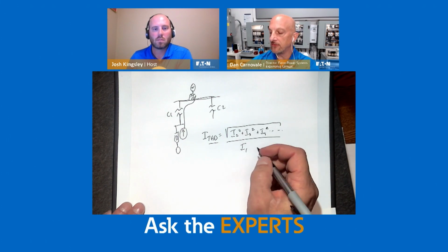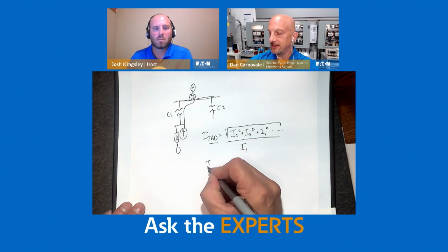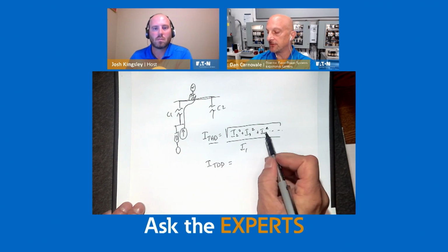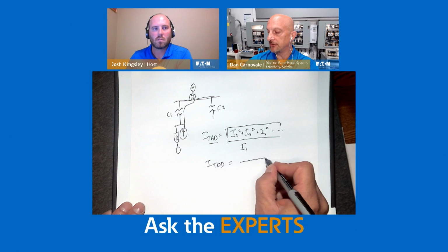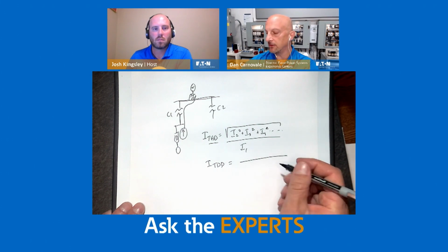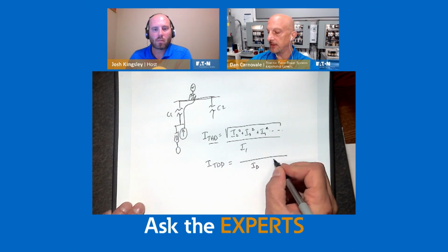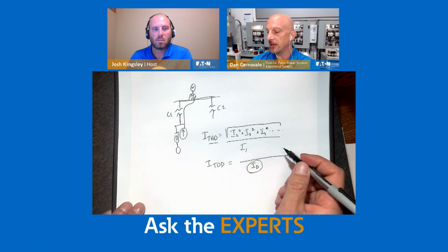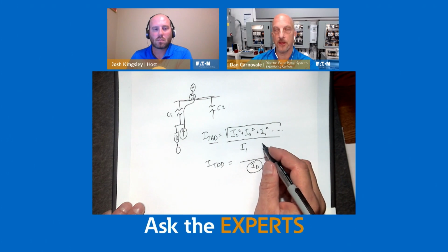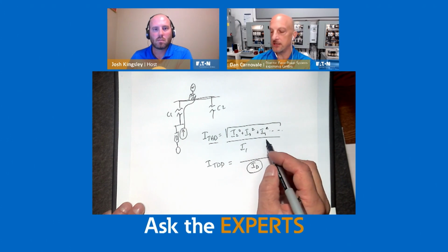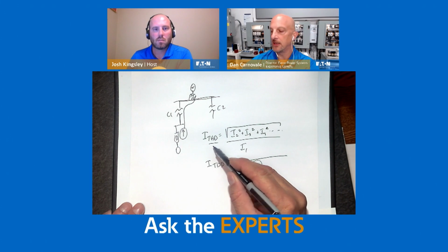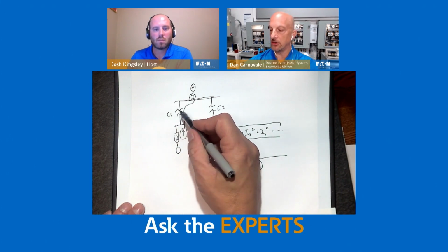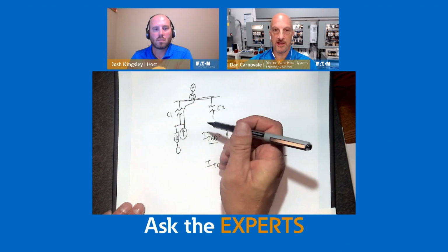With the IEEE 519 standard, they change that to ITDD, total demand distortion. And what that means is everything on the top is relatively the same, except you're using kind of a worst-case scenario demand. And then this is the demand situation when you're at your peak. So you might have really light distortion, let's say in terms of amps overnight, but the THD could be very high. But your TDD is what's important. So how badly are you screwing up the current on the system according to the size of the system?